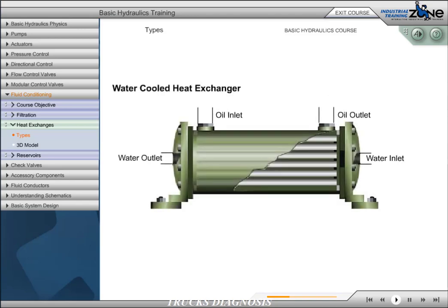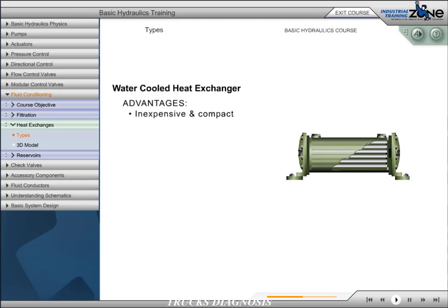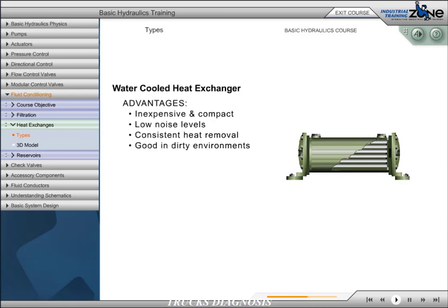If cooling water is available, a shell and tube heat exchanger may be preferred. Cooling water is circulated through a bundle of bronze tubes from one end cap to the other. Hydraulic fluid is circulated through the unit and around the tubes containing the water, and the heat is removed from the hydraulic fluid by the water. The advantages of this type of cooler are: they are the least expensive, very compact, they do not make noise, they provide consistent heat removal year-round, and they are good in dirty environments.